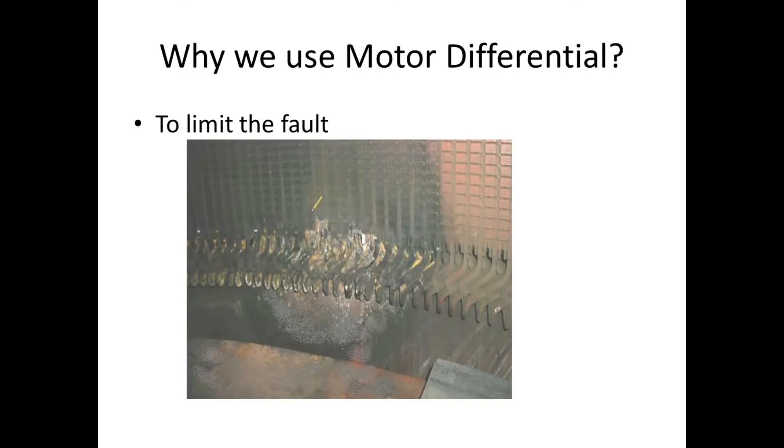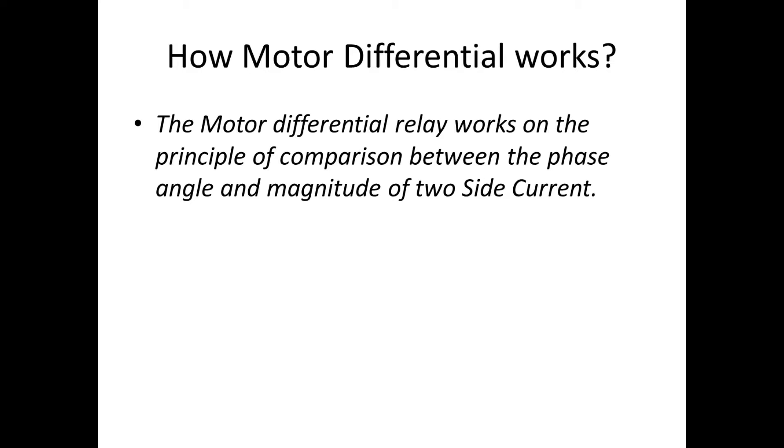Second, how does motor differential work? For this question, the motor differential relay works on the principle of comparison between the phase angle and magnitude of two side CTs. That is phase side current and neutral side current.